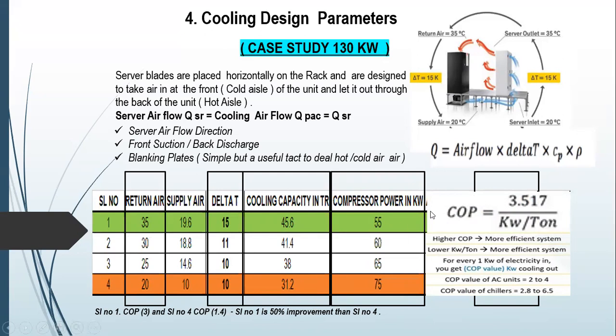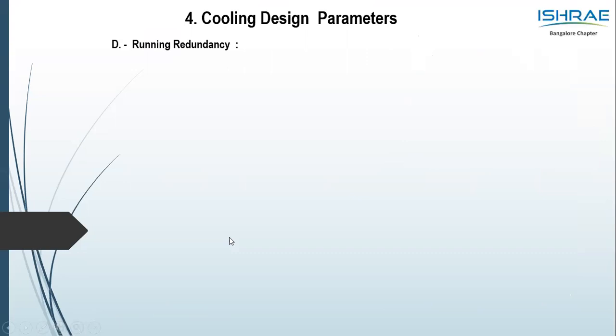Very important to note. Again, referring back to the ASHRAE, I have just taken close to, here it is 18, it is just 19, but you can technically still go higher than that. ASHRAE says 18 to 27. So technically you can actually increase it and maintain a delta T of 15. So that's on the ASHRAE norms.